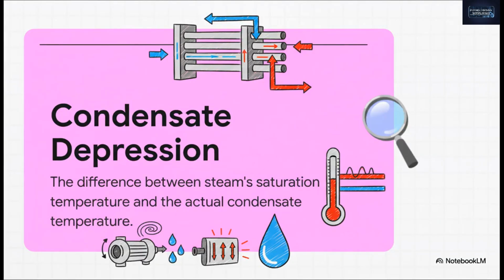Now here's a cool bit of engineering jargon for you: condensate depression. This is basically how much you overcool the water after it's already turned back from steam, and it's a real balancing act. You actually want to cool it a few extra degrees to stop dangerous vapor bubbles from forming in your pumps. But if you cool it too much, you've just wasted a bunch of energy because now you have to spend more energy to heat it back up again for the next cycle.